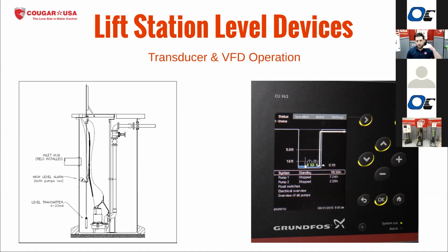We can do our on and off points at whatever level we want. So anytime we have a triplex system, we move to this. Otherwise, we'd have way too many floats. If we're using VFDs, things like that, you do want to potentially have this so that you can do some different things with the speeds of the pumps. So there are some issues that might happen with the transducer. I mean, it's in a pretty nasty environment, so it is going to have a usable life there.